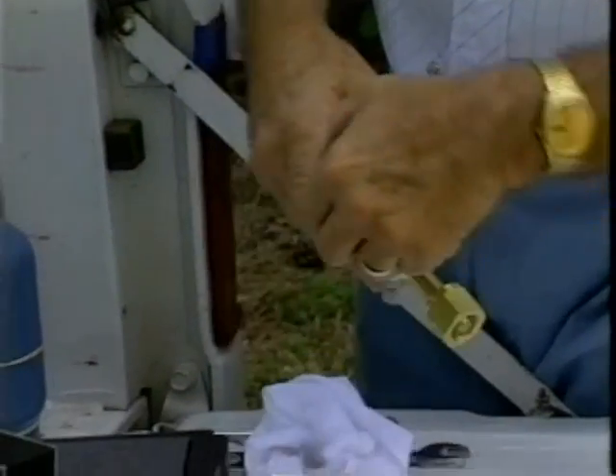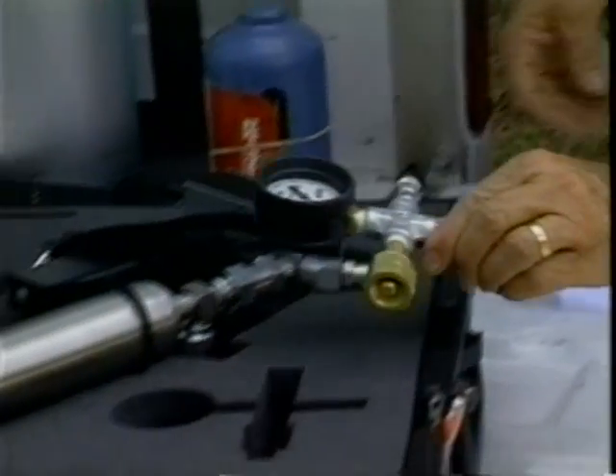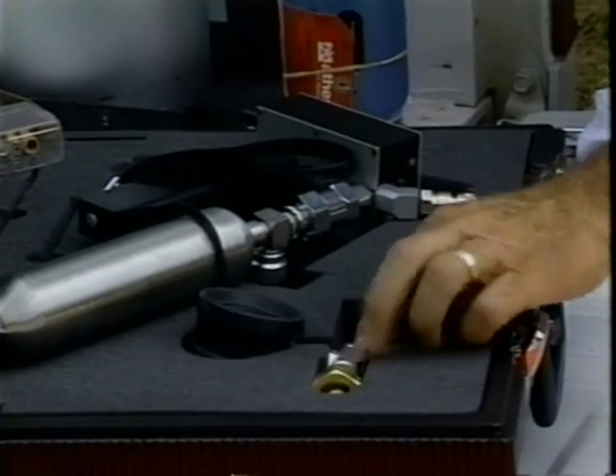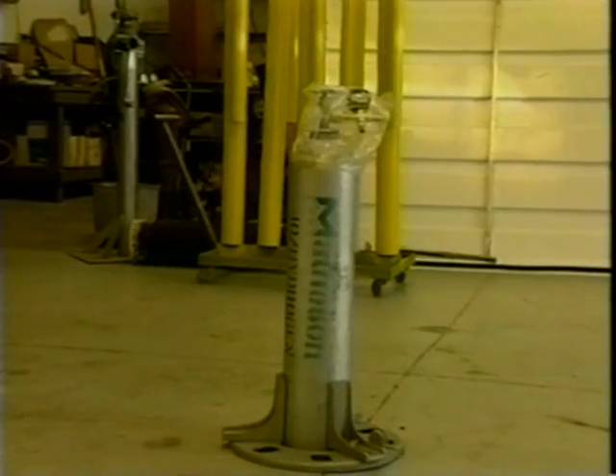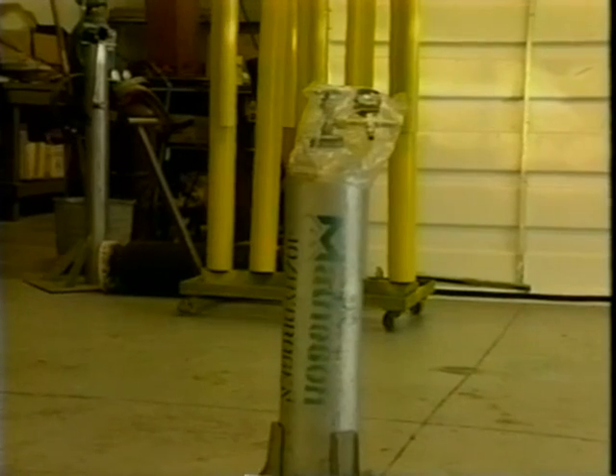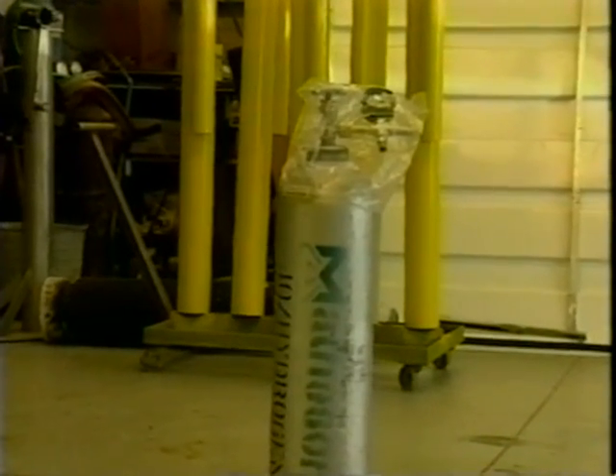In normal operations, the refill assembly should be removed, cleaned, and stored in its case. If the refill assembly is to remain mounted on the cylinders, it should be covered with a plastic bag. This will prevent dust from settling on the fittings and accidentally being blown into the unit during the refueling operation.